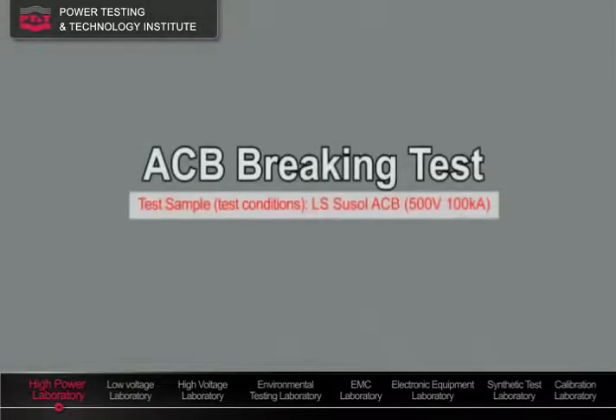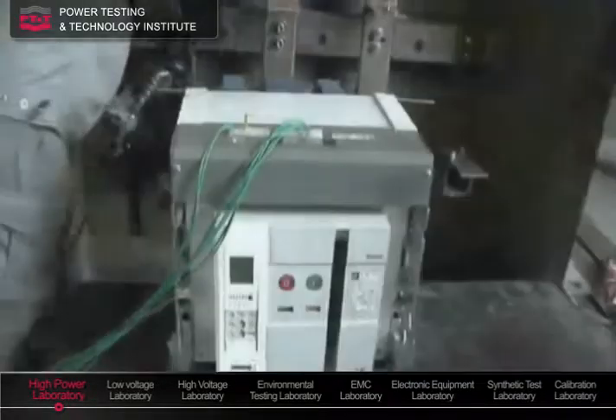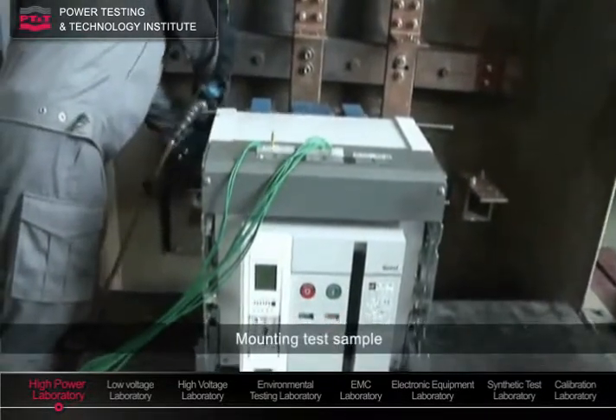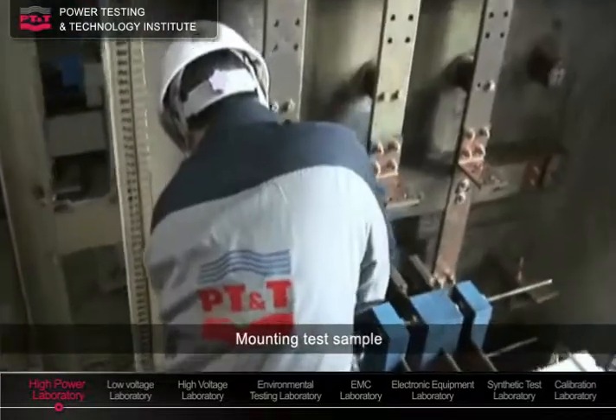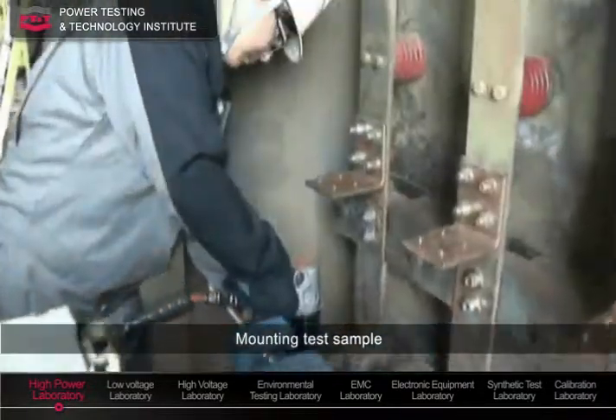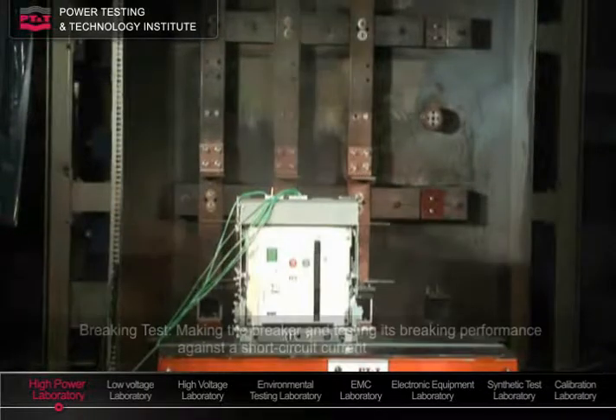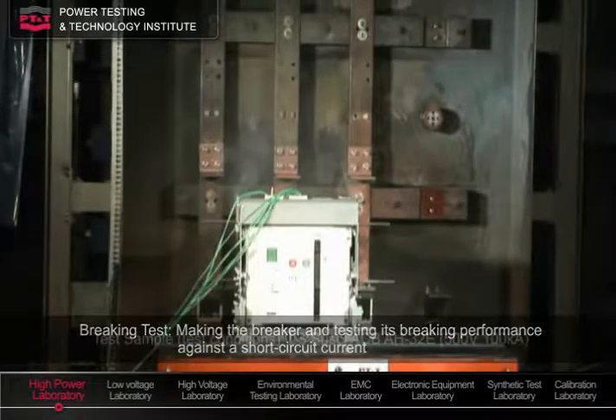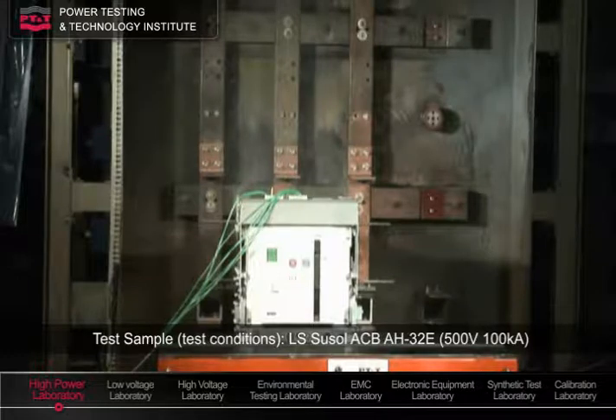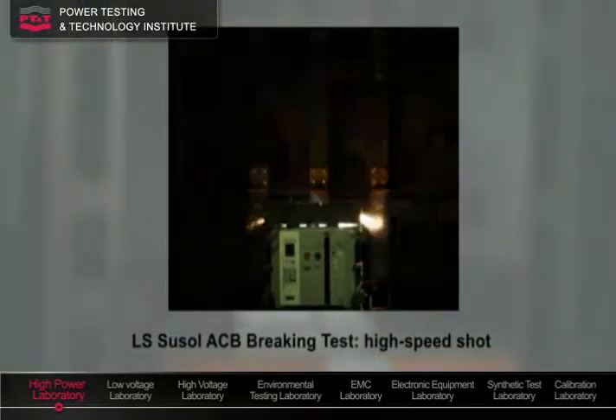This is a successful case of an ACB breaking test. ACB is installed on a base plate and connected with bus bars based on the rated current to build the short-circuit testing circuit. LS Susol ACB has successfully cleared the test current without any damage on its appearance.